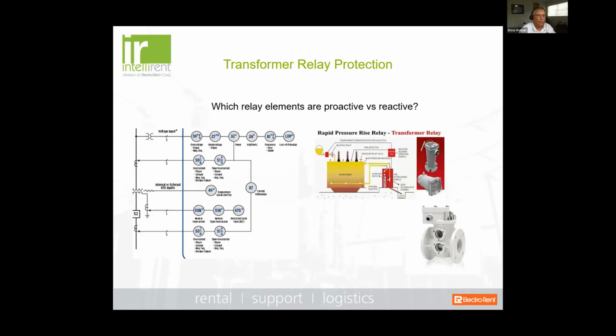I think it's important to understand that when you talk to protection engineers and test technicians about protective relaying, you're thinking, well, my transformer is well protected. I've got a very modern multifunction protective relay protecting the transformer, as well as the Buchholz relays and rapid pressure relays that you'll see in the slide over here. And then what we have to realize is that there are some protective elements for a transformer that are both proactive and reactive. Now, what do I mean by that? Well, consider a differential relay. A differential relay is looking at the current coming in and the current going out, and based on Kirchhoff's law, that should be equal, all things being considered. If it's not, that means there's a fault internal to the transformer, and you create enough differential current between the two windings to trip the relay and take the transformer offline.